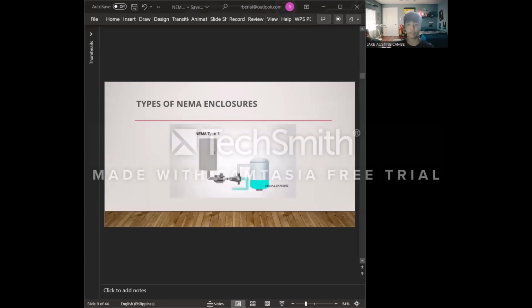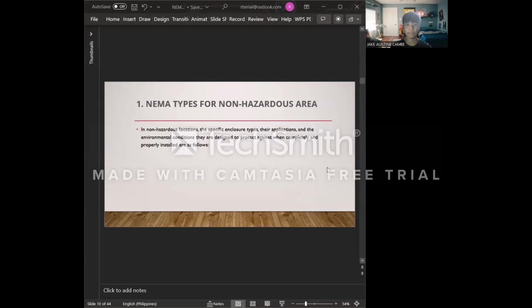So, types of NEMA enclosure. Dito, let's look at the different levels of NEMA ratings. NEMA ratings for non-hazardous locations go from 1 to 6 and 11 to 13, while yung NEMA ratings for hazardous locations go from 7 through 10. Number 1, NEMA types for non-hazardous areas. It means that in non-hazardous locations, the specific enclosure types, their applications, and their environmental conditions they are designed to protect against when completely and properly installed.